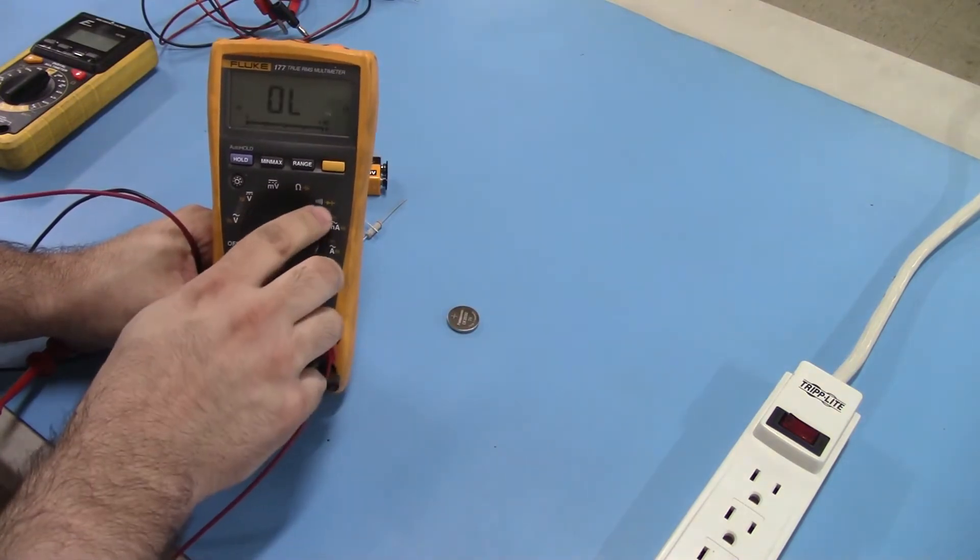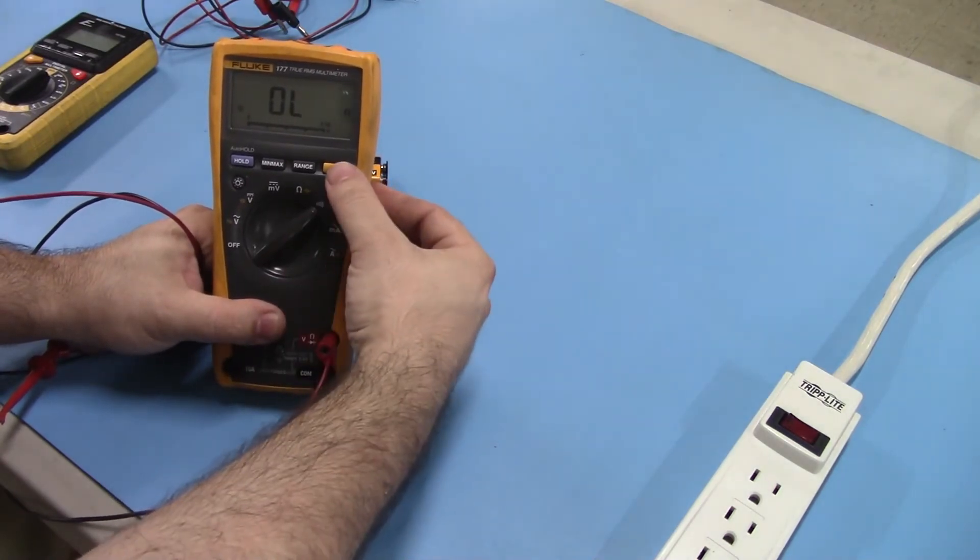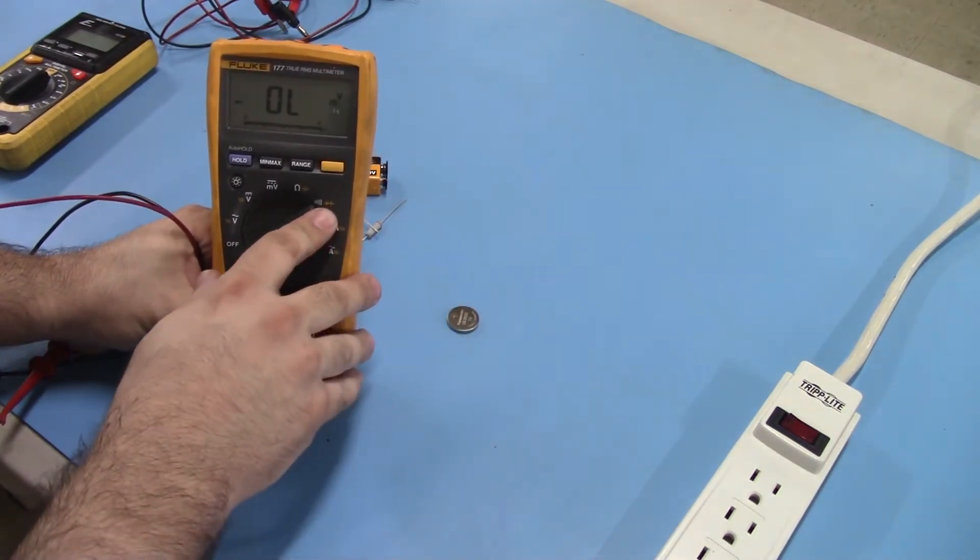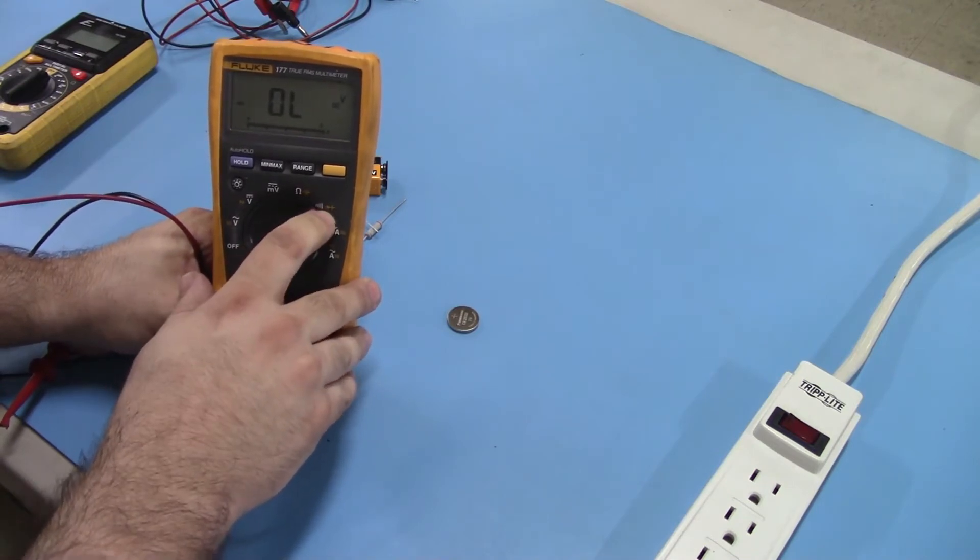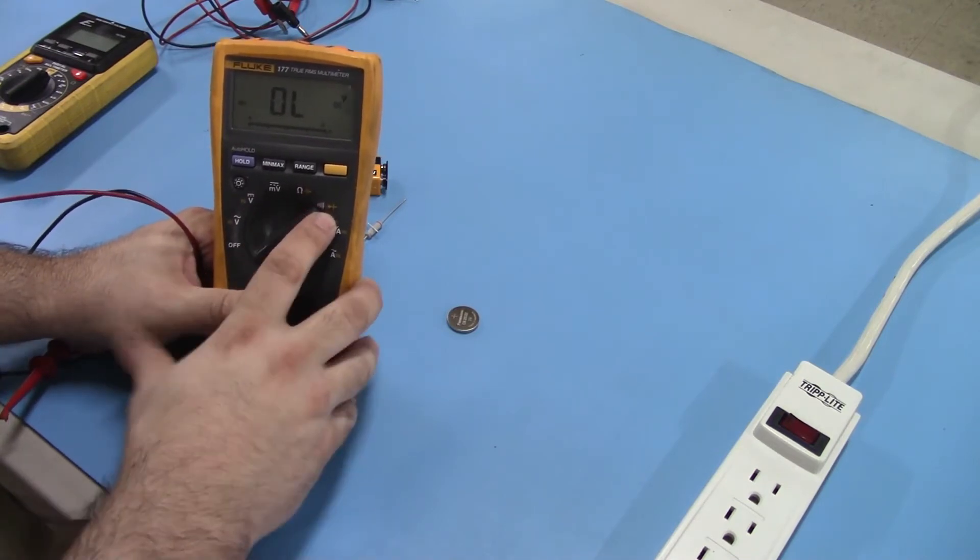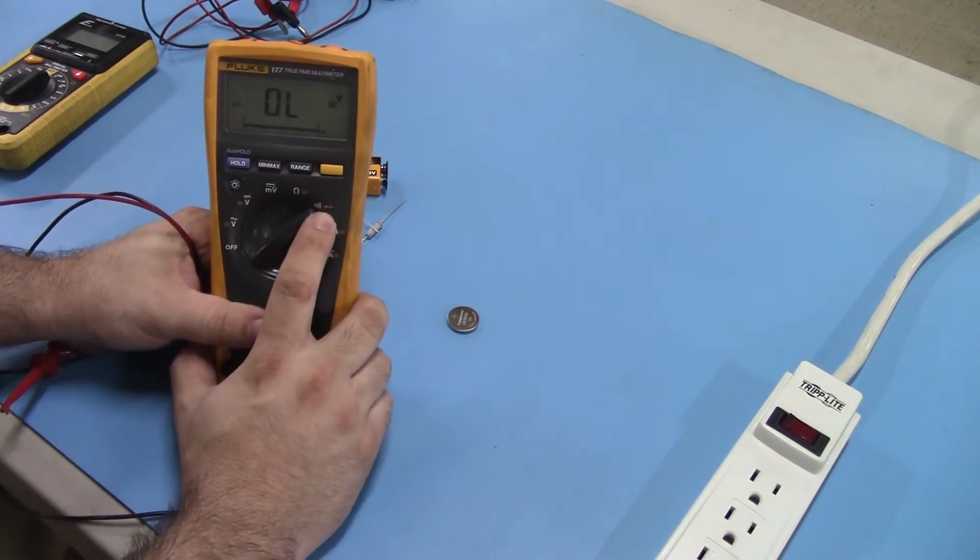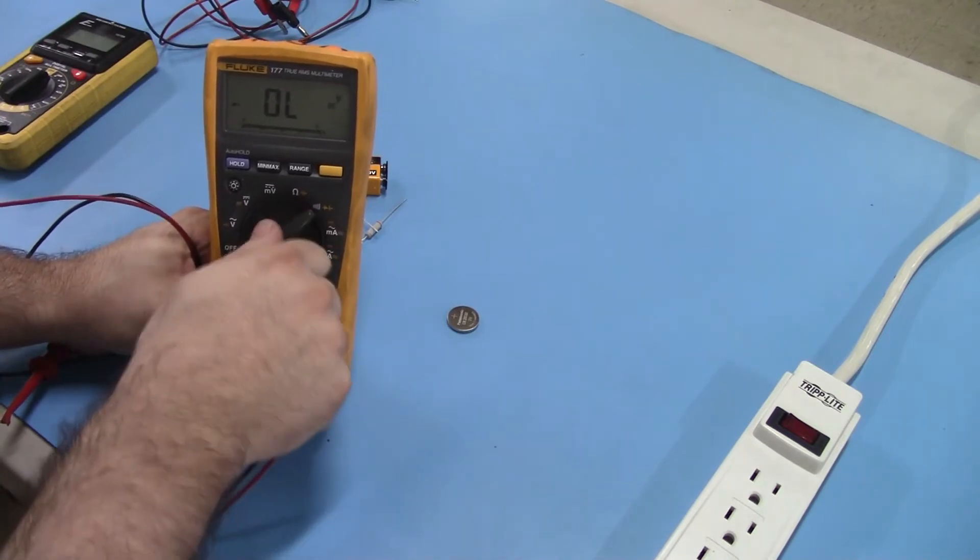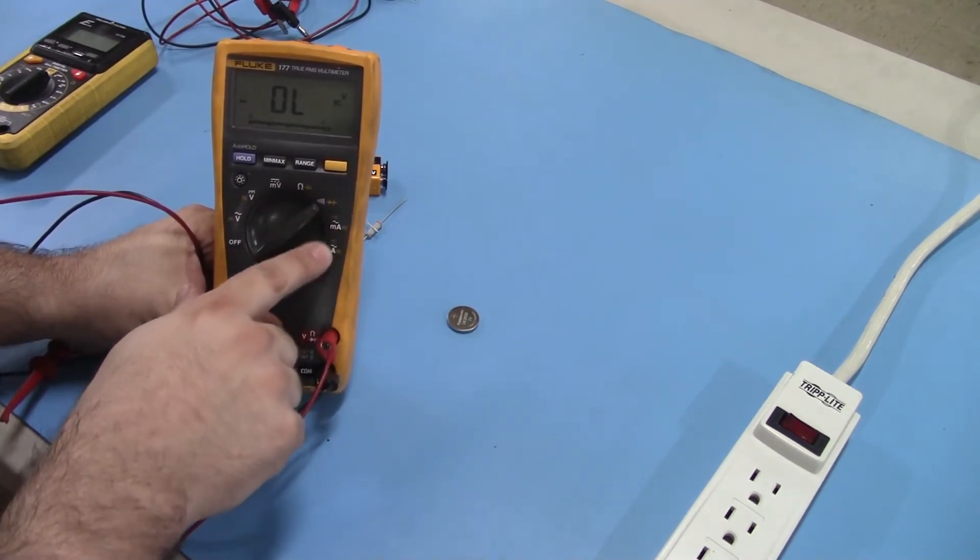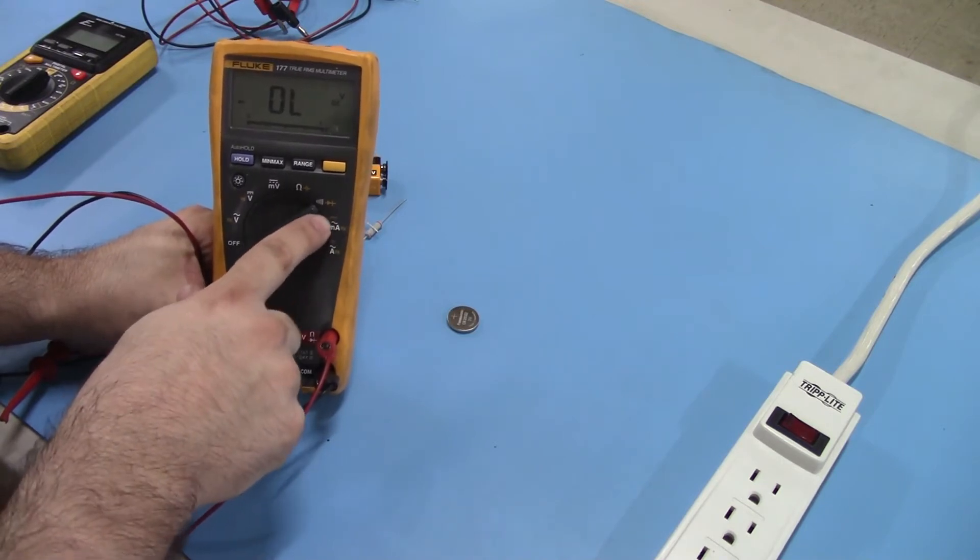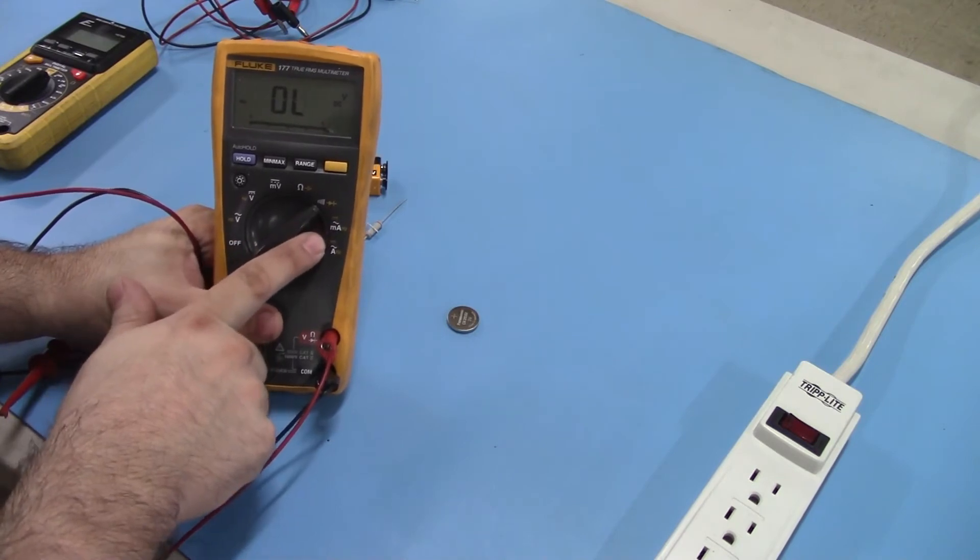Your next position here, that's a diode symbol. When you go to continuity and hit your shift button, that puts you in diode check. Diode check you probably won't run into too much, but it is a product of volts. So what you're actually measuring is your voltage or your voltage drop through the diode. And as you can see here, hertz over here, DC as well. You can shift your mode from AC to DC on your amp scale also.